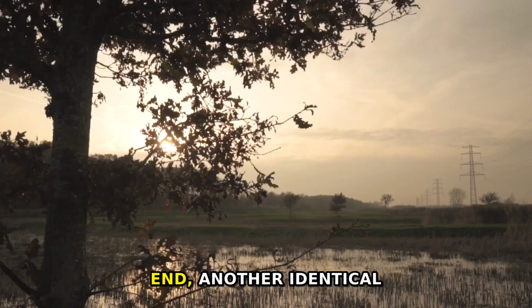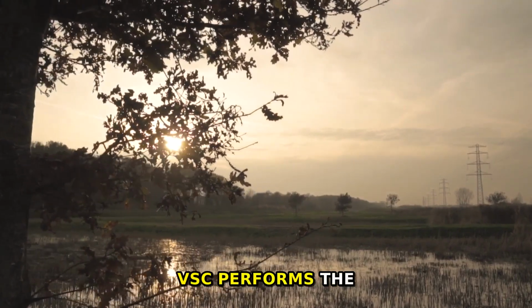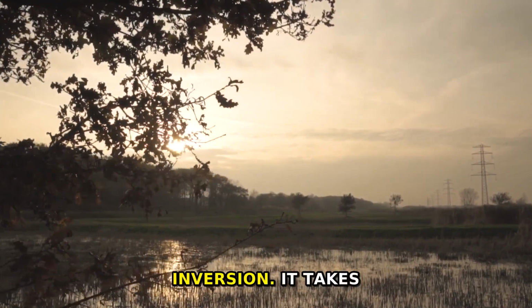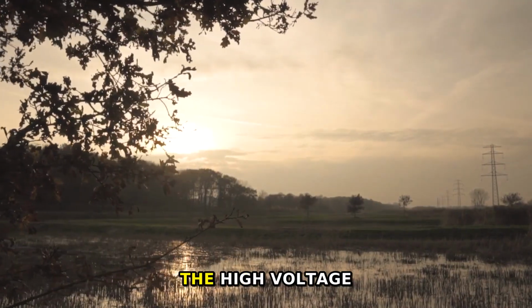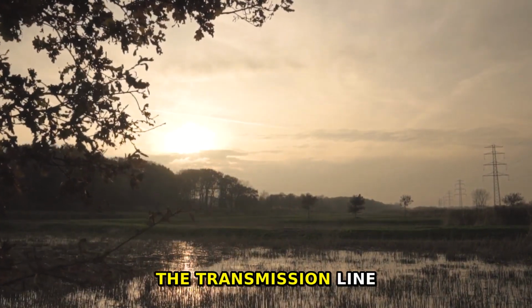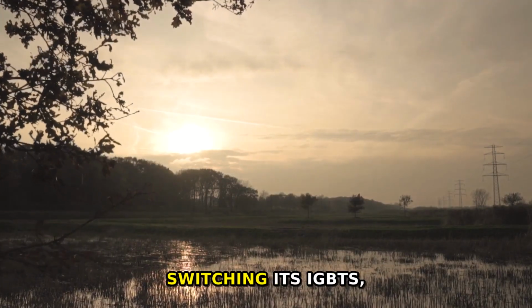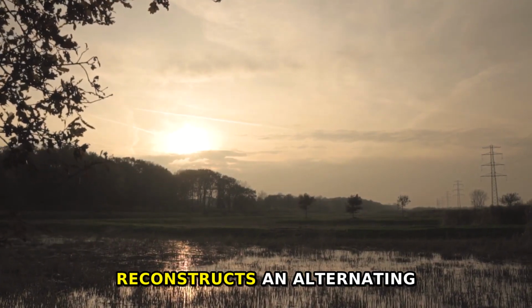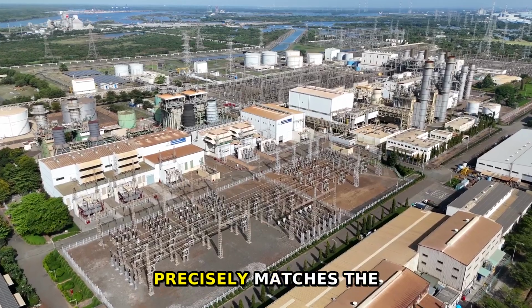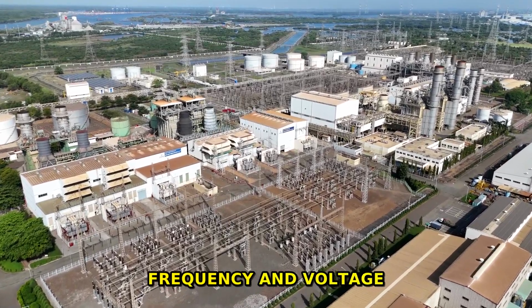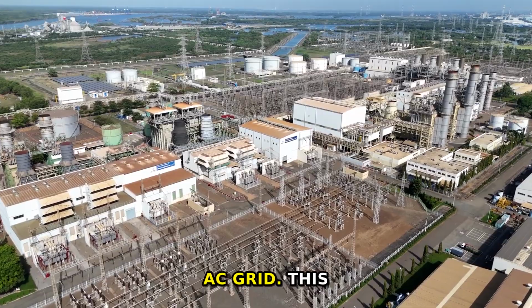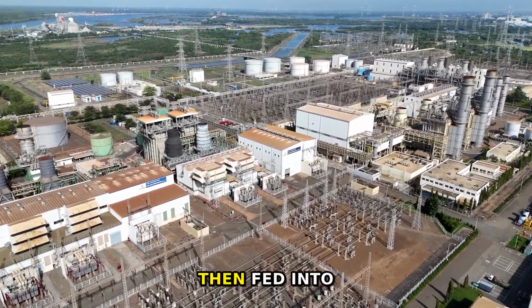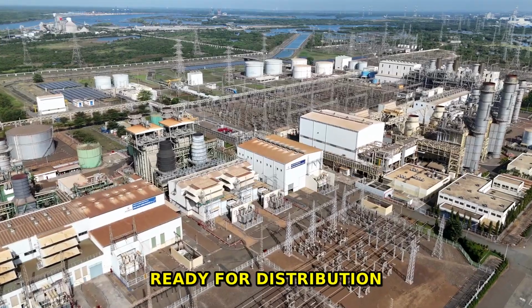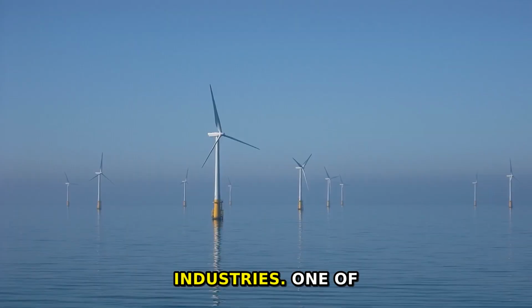At the receiving end, another identical VSC performs the inverse operation, called inversion. It takes the high-voltage direct current from the transmission line and, by rapidly switching its IGBTs, reconstructs an alternating current waveform that precisely matches the frequency and voltage of the local AC grid. This AC power is then fed into the local grid, ready for distribution to homes and industries.